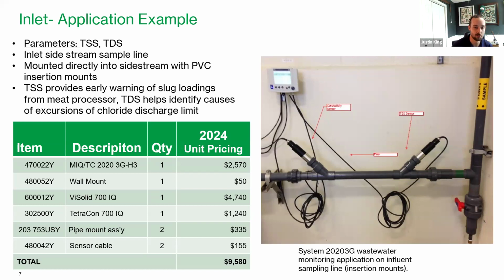And then they also used a conductivity sensor to measure TDS, which helped them identify causes of excursions of chloride discharge limit. The TDS can be used for a compliance measurement, especially where there are industries that dump high levels of dissolved metals, because high levels of dissolved metals can definitely disrupt wastewater treatment processes.